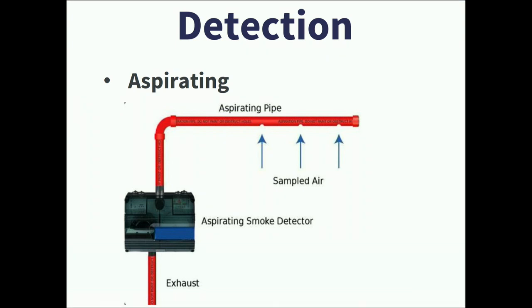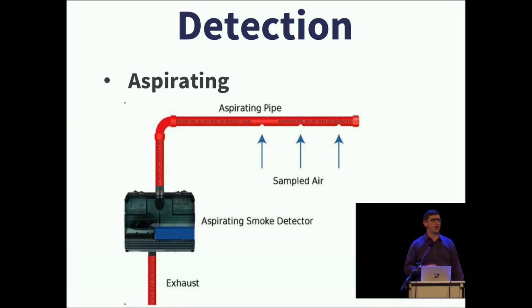Now, in data centers, you'll often hear about VESDA or IFD, VESDA being very early smoke detection apparatus, and IFD, incipient fire detection systems. These are basically sniffing the air constantly, and you'll see the red pipes generally around the top of air conditioning units or anywhere where there's good airflow going. These systems are super, super sensitive, anywhere between 500 to 1,000 times more sensitive than the optical and ionizing smoke detector heads.